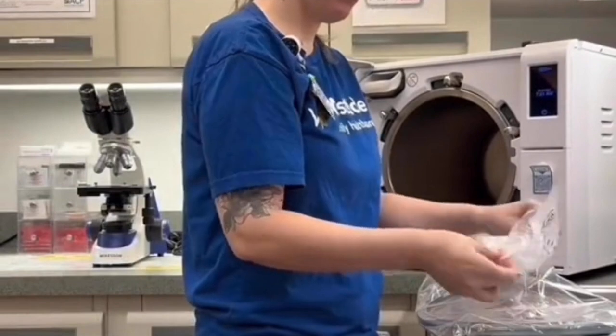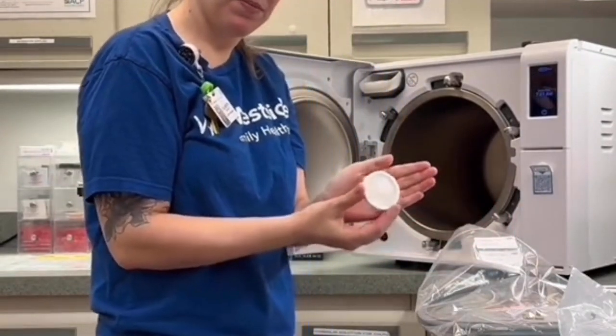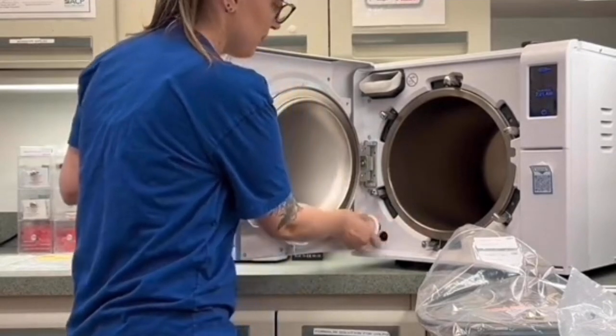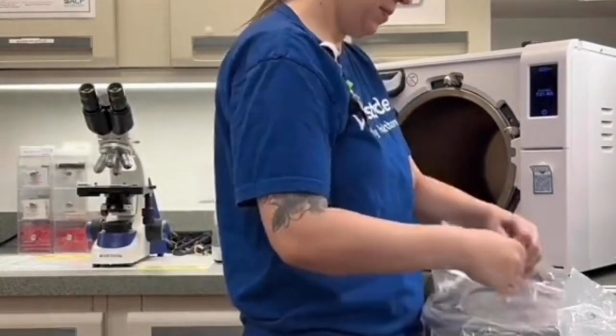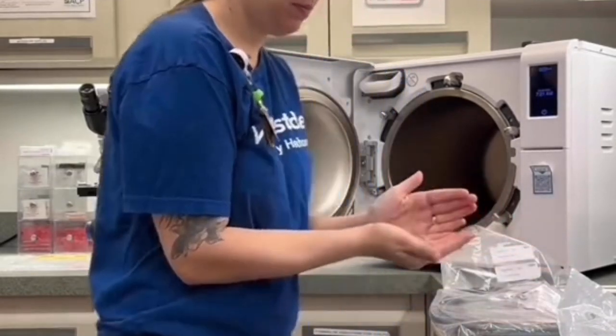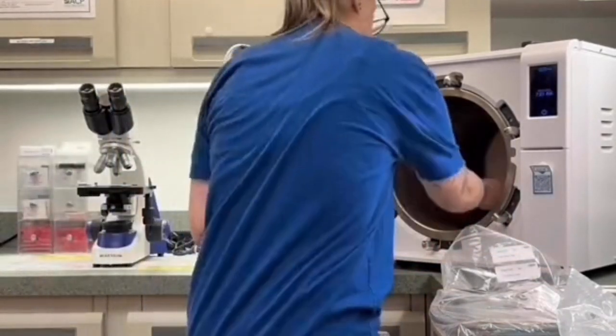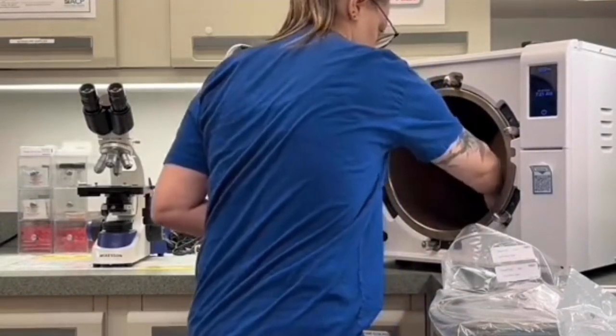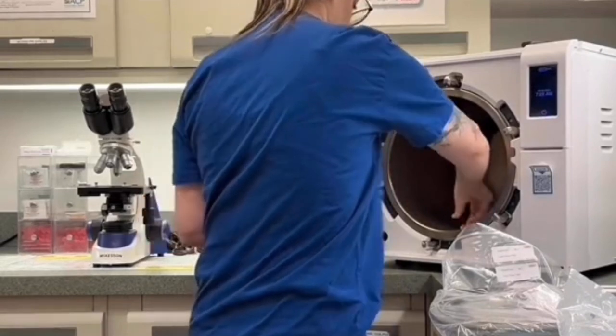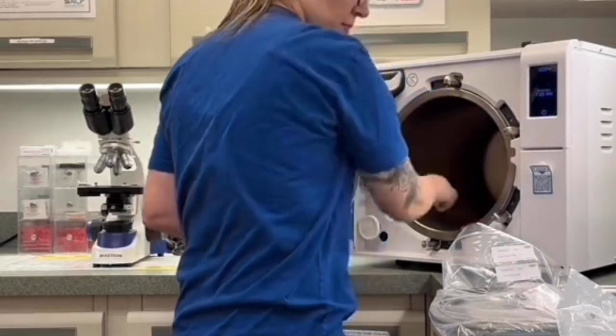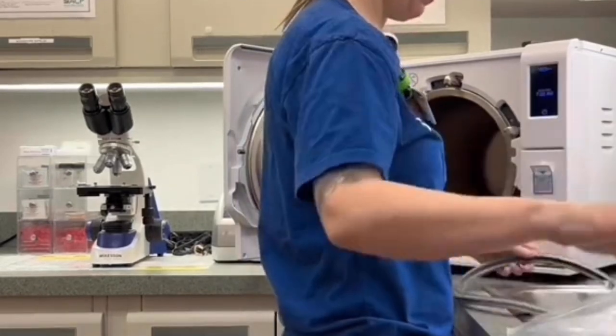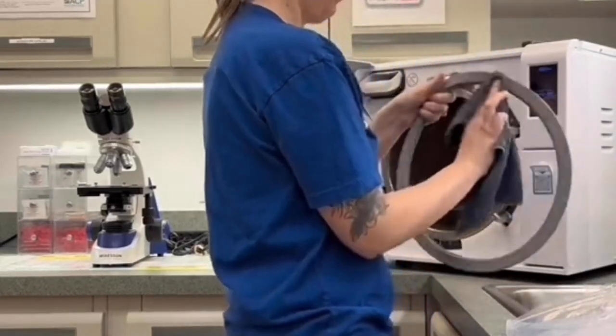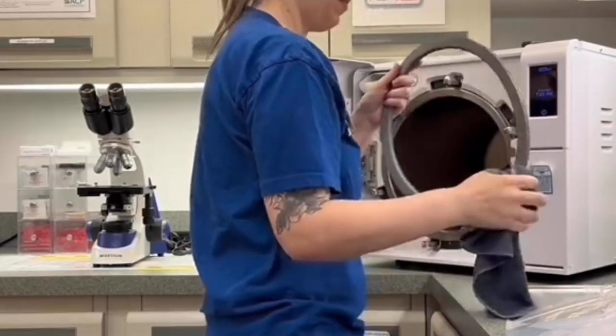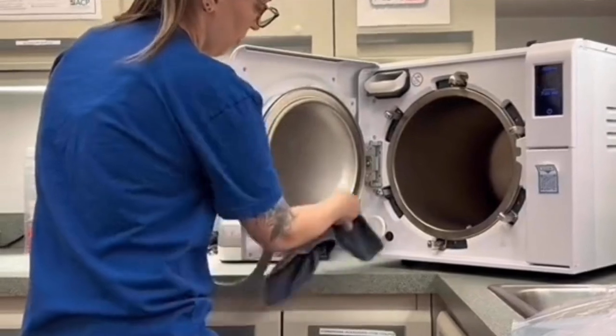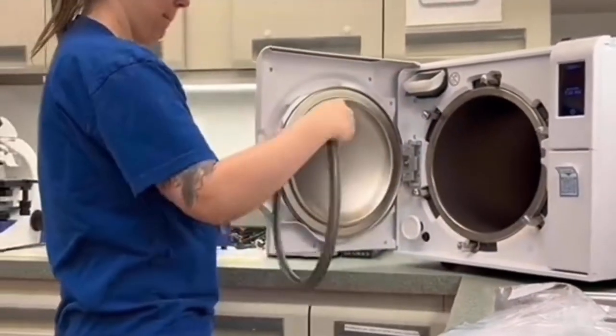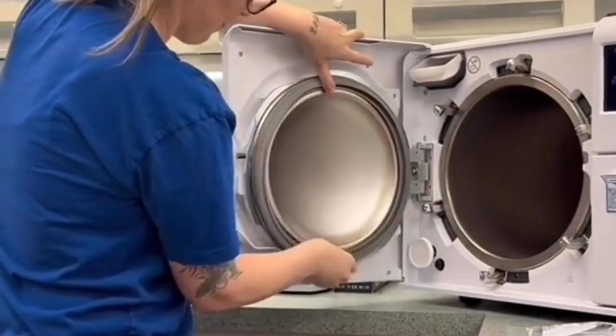With the new kit, replace the HEPA filter, the 3 chamber filters and the door gasket. Be sure to have the door gasket slightly damp, making it easier to place. Start at the top and place the gasket in at an angle so it fits in place. Do the same at the bottom of the gasket, followed by the sides.